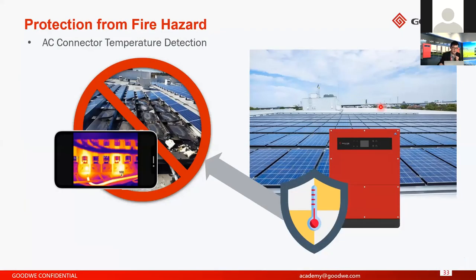And here is the AC connector temperature detection. Actually, it's an optional function of GoodWe. If you want to use this function, you need to order the inverter with this function. We have a sensor on the AC side, and this sensor will detect the AC connector temperature. If the temperature of the AC connector is higher than our limit, the inverter will shut down automatically and immediately to protect the AC connector and also to avoid a fire problem.